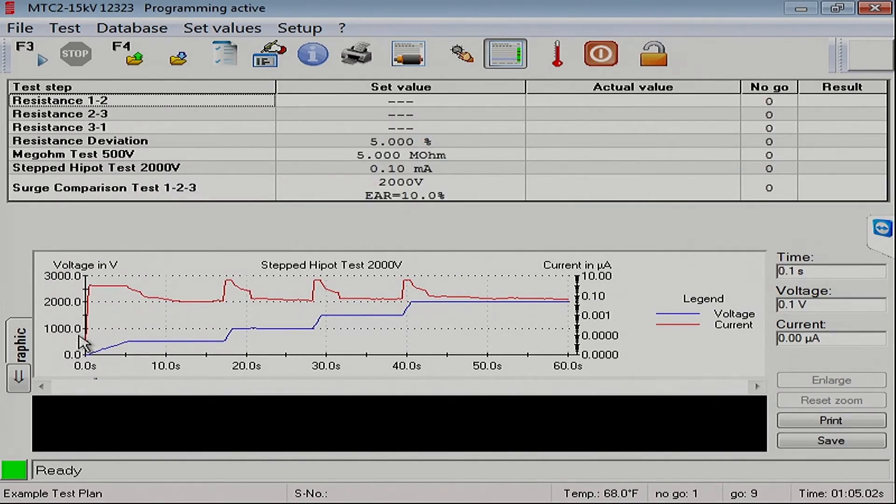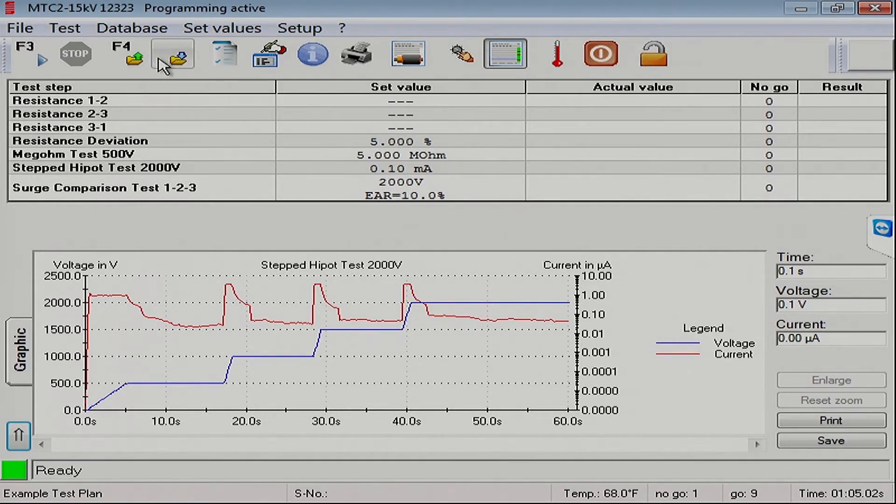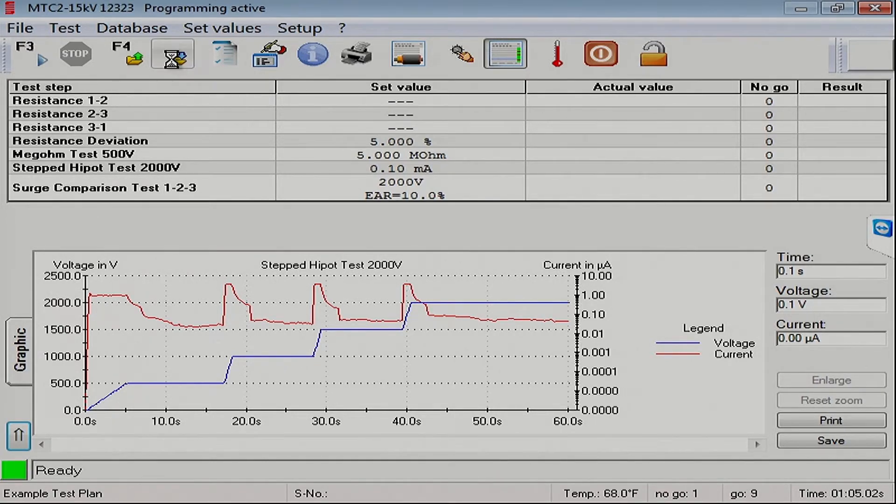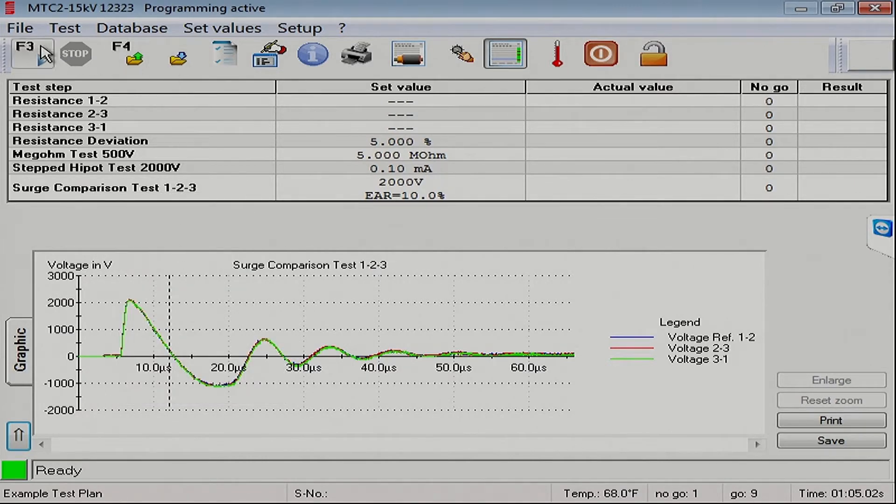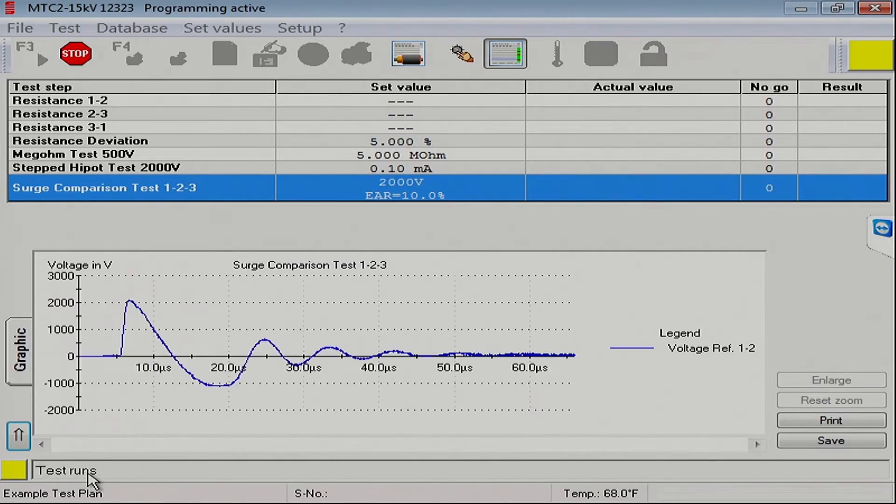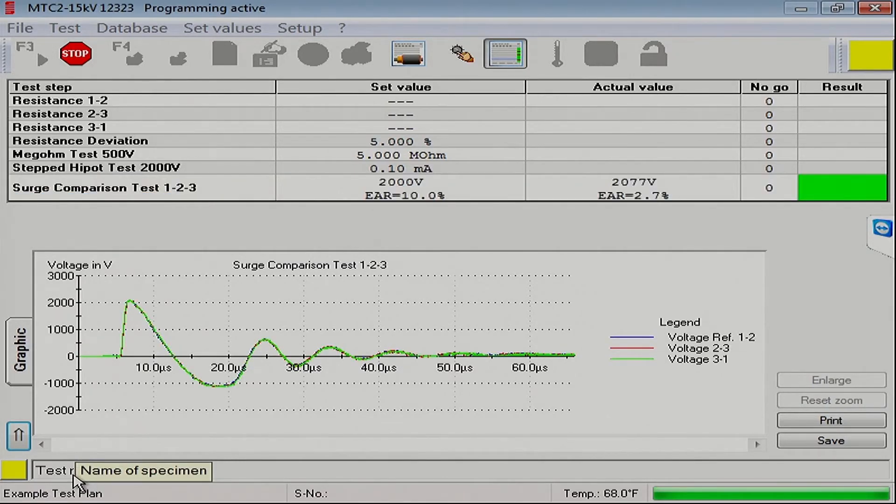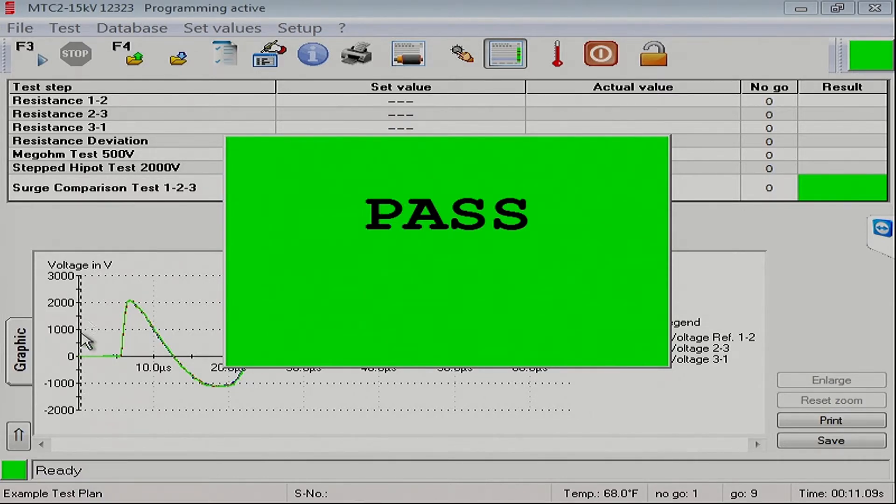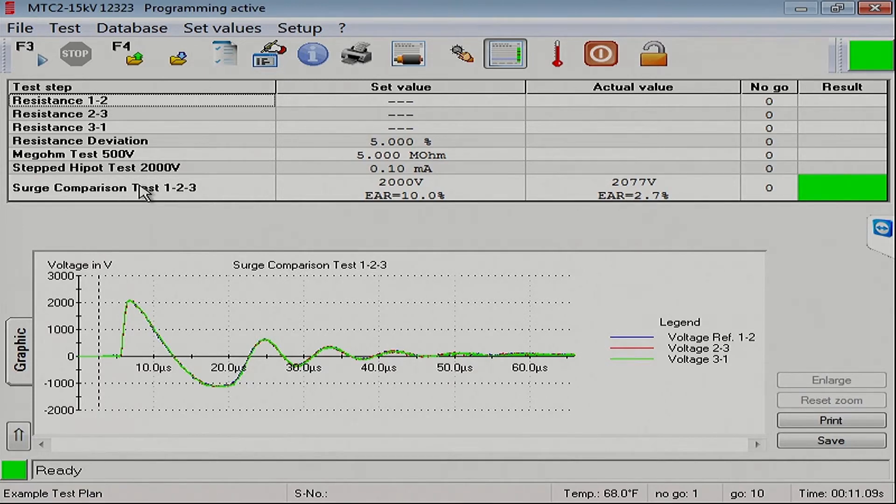There we go. We have ourselves a surge comparison test. I will save this test plan, and we will run just this one step to see how it goes. Press the go button. You can see in the lower left-hand corner, the surge test is running, and it was adjusting the test voltage since we said we wanted to automatically regulate the voltage. And we've got a good pass here. Here we have a resistance test, a megohm test, a stepped hipot test, and a surge comparison test.